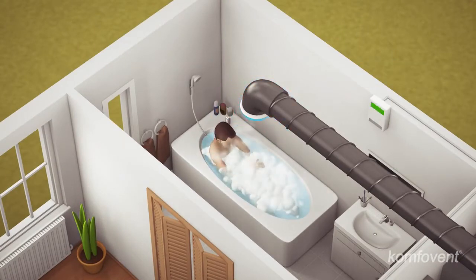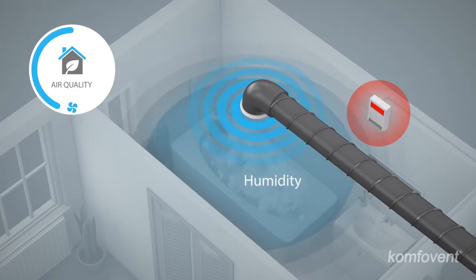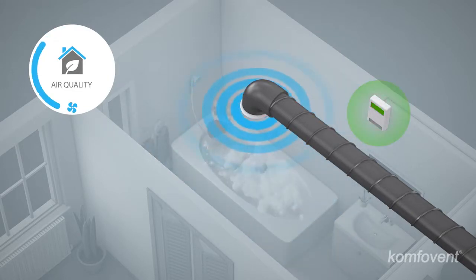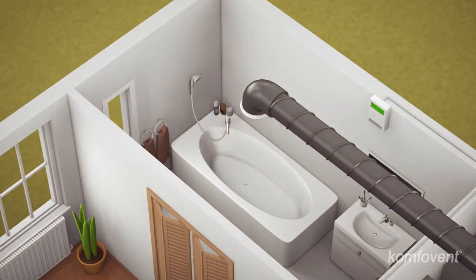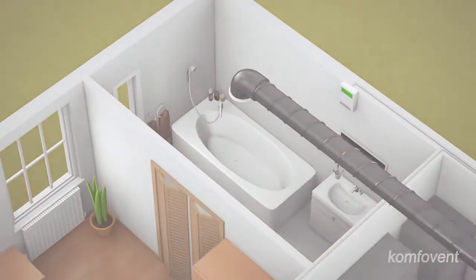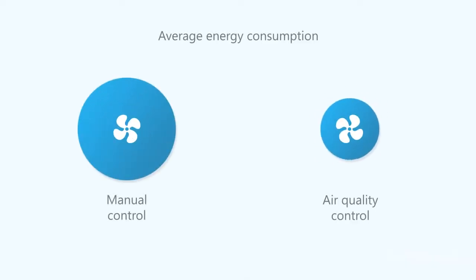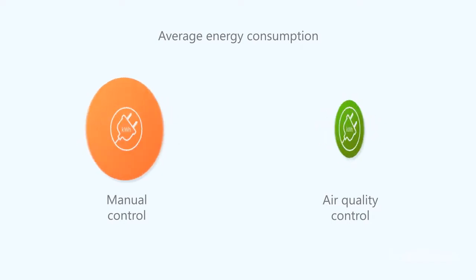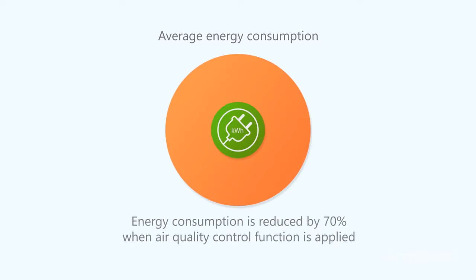An indoor humidity sensor measures relative humidity, and if the threshold limit value is exceeded, it increases the intensity of ventilation, thus removing excess moisture from the rooms. It has been estimated that a ventilation system functioning on demand reduces annual energy consumption of the unit up to three-fold.